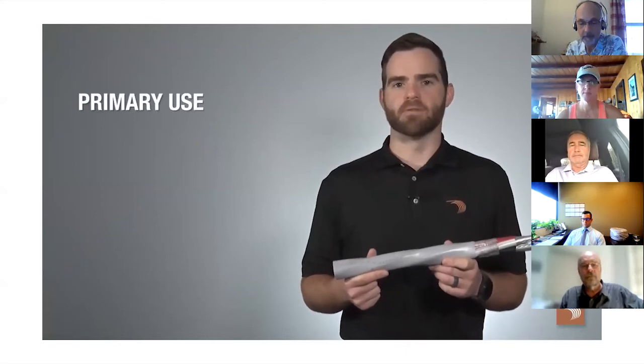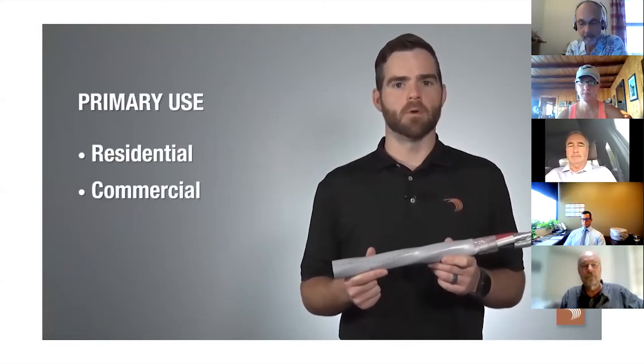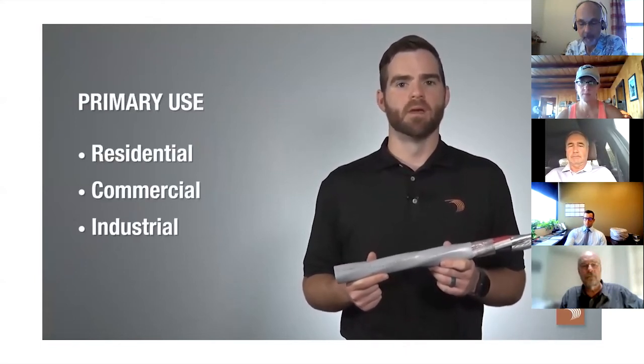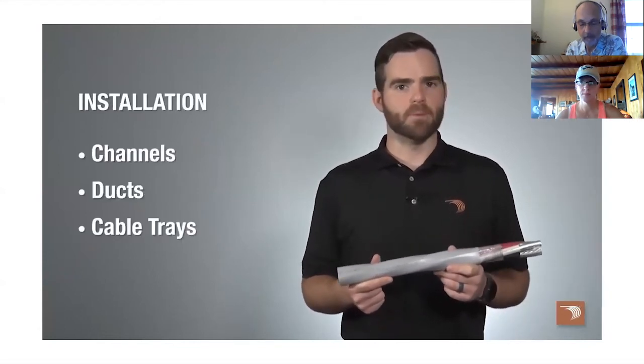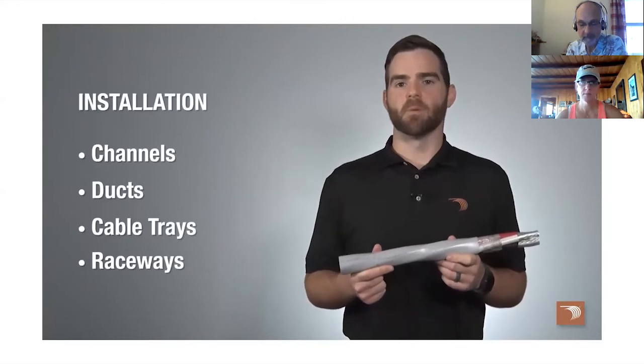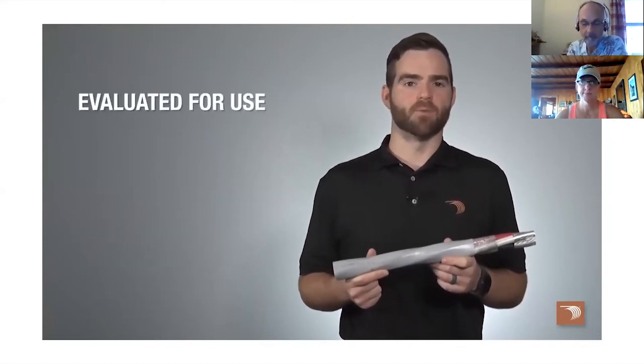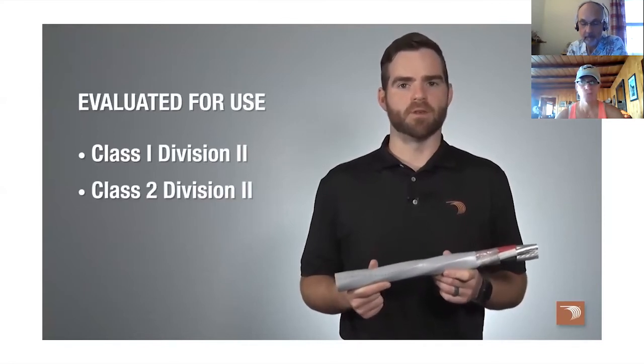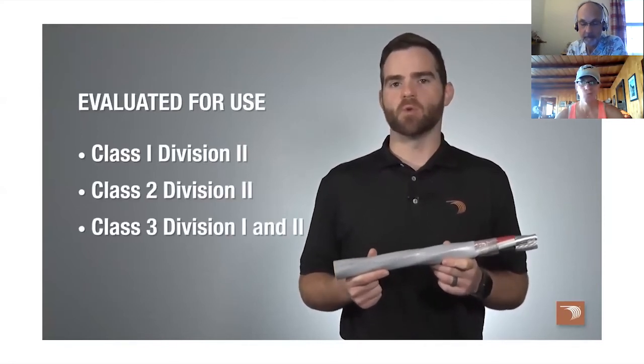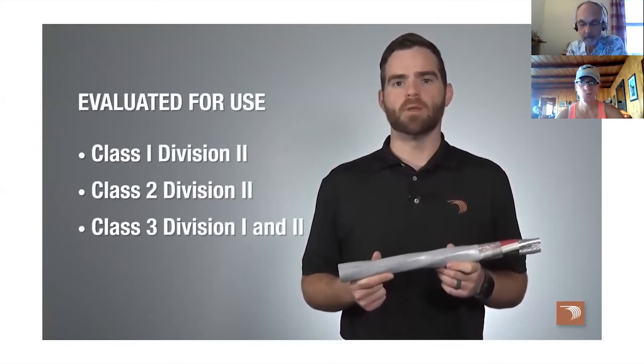Tray cable SER hybrid cable is primarily used for connecting power devices in residential, commercial, and industrial environments. It's suitable for installation in channels, ducts, cable trays, and raceways, and is permitted for 600-volt applications. It's evaluated for use in Class 1 Division 2, Class 2 Division 2, and Class 3 Division 1 and 2 locations when utilized with listed fittings rated for the condition of use and exposure.